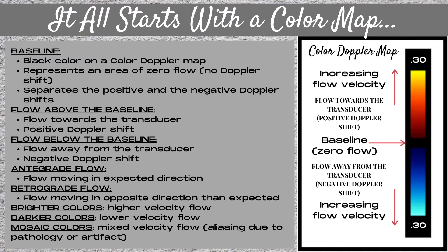The first color is black. The black color on a color Doppler map is the baseline. This represents an area of zero flow where there's no Doppler shift, and it separates the positive and the negative Doppler shifts. Flow above the baseline, or above the black color, represents flow towards the transducer, or a positive Doppler shift.